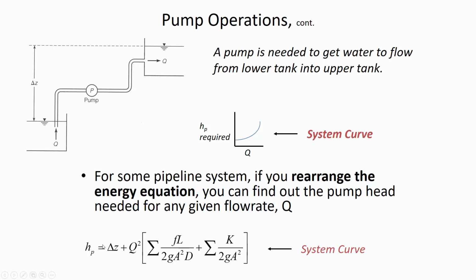The delta Z is the same regardless of what the flow rate is, but we could do a graph of this system curve. And the system curve is just the energy equation, where point 1 is the lower reservoir and point 2 is the upper reservoir. And since the velocity in both reservoirs is 0, we canceled out the velocity head term of the energy equation. And since both of these reservoirs are open to the atmosphere, we are omitting the pressure head term, and all that's left is the delta Z between the two, and then the losses. So we've rearranged the energy equation to solve for H sub P. This is the pump head required to achieve a certain flow rate when you've got a pipe length of L and so on, the parameters that are here.